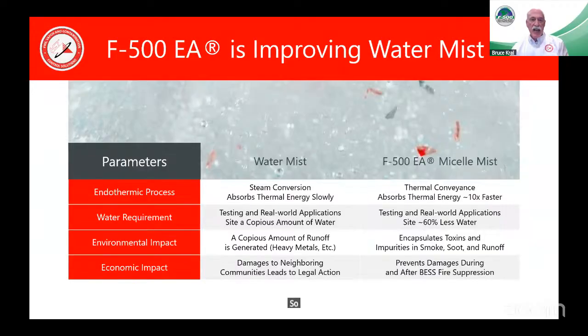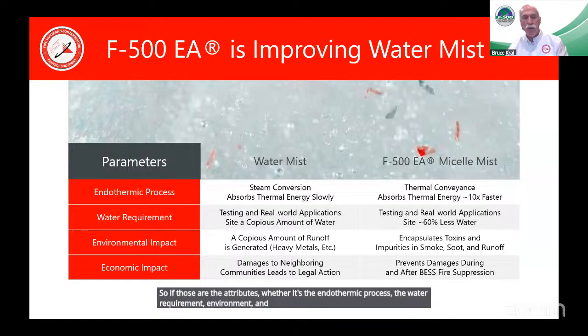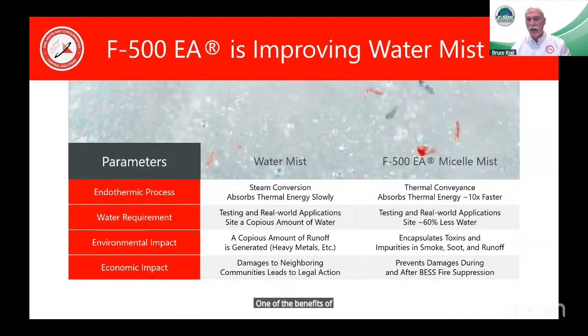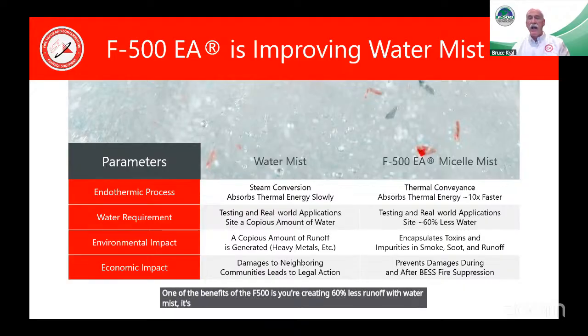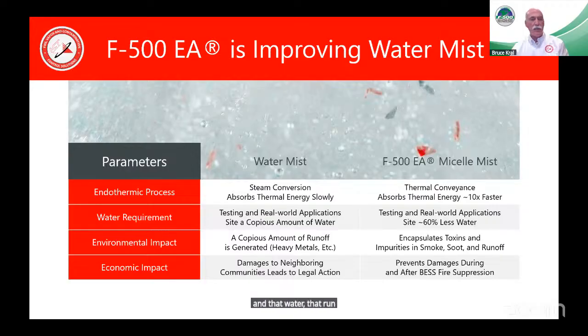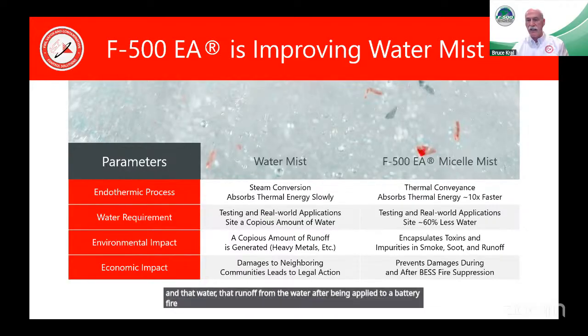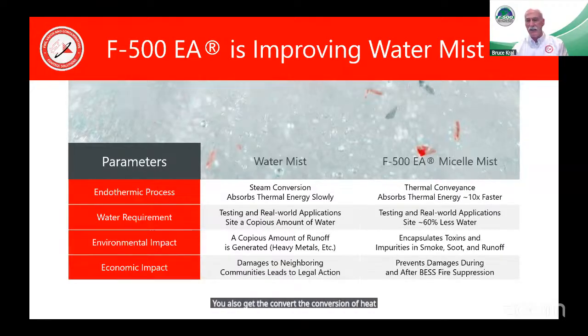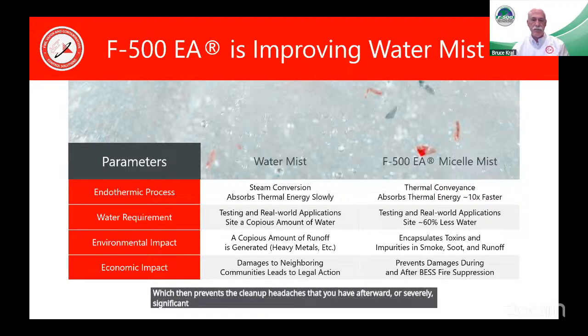So those are the attributes, whether it's the endothermic process, the water requirement, environment, and economics. One of the benefits of the F500 is you're creating 60% less runoff. With water mist, it's even less. And that runoff from the water after being applied to a battery fire is toxic and contaminated. You also get the conversion of heat 10 times faster while you're encapsulating the toxins and impurities in the smoke, soot, and runoff, which then prevents the cleanup headaches that you have afterward or significantly reduces them.